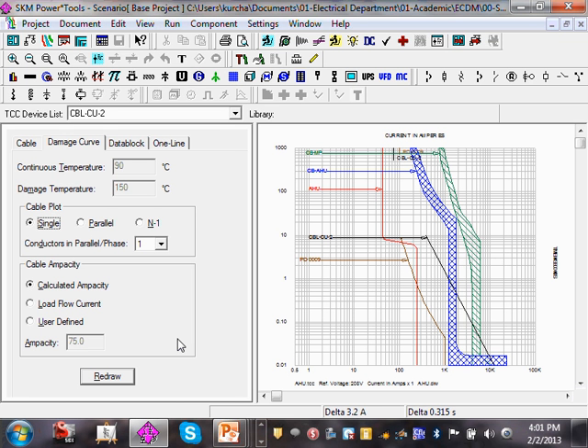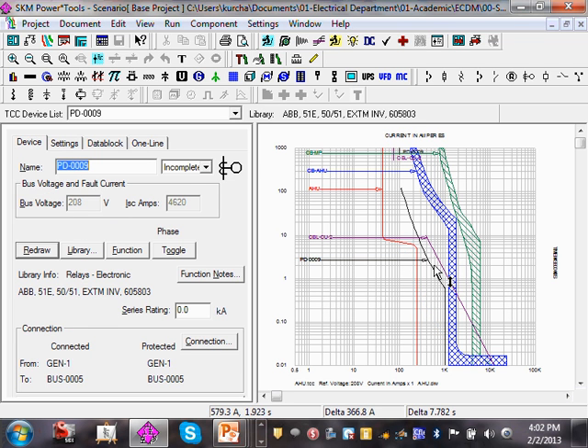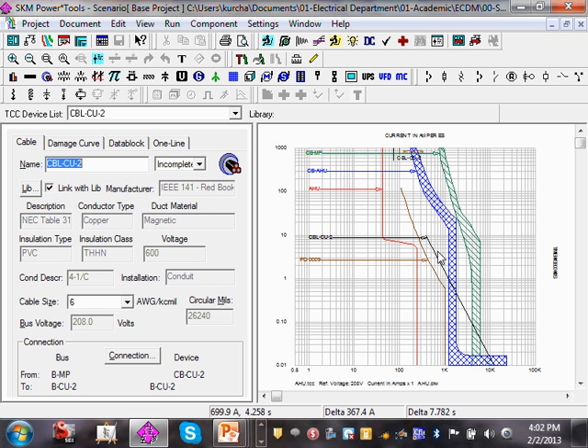After 1.5 seconds, guys, if the circuit breaker does not trip, what's going to happen? Vaporize. That's the word that we like. So that conductor is going to vaporize. That's basically what the damage curve for cables is. Is that blue curve protecting that, or which? The one that protects the conductor right now is the blue curve.